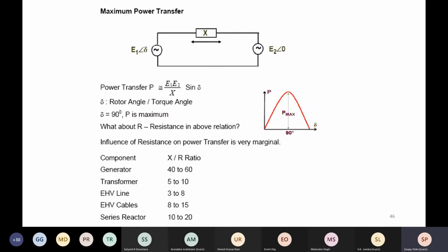Okay, so I talk about the power transfer relationship with sine delta. Delta, as I explained to you, is the internal angle between the EMF of the generator and the terminal voltage of the generator. This becomes your synchronous reactance of the machine. And the power transfer is basically this equation, E1 E2 over the reactance times sine of delta, and this is then the curve. Your power transfer is maximum when delta, the load angle, is 90 degrees. Sine 90 is 1, so the maximum power can be generated when delta is 90 degrees. Above 90 degrees, the machine will become unstable.